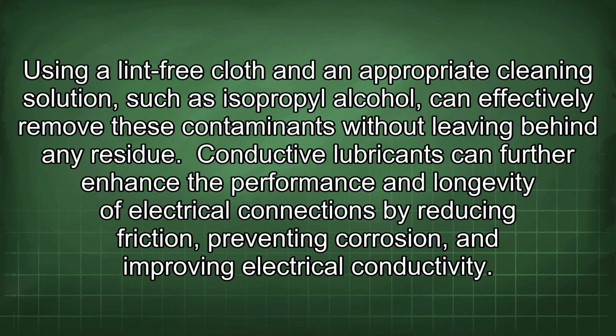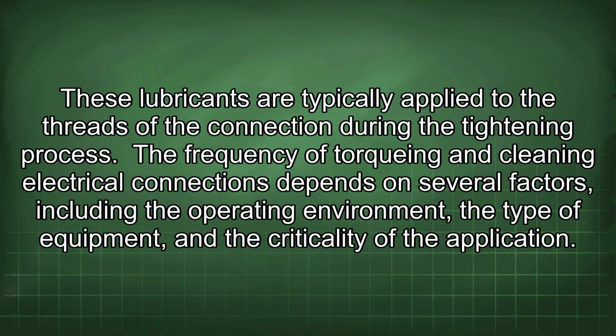Using a lint-free cloth and an appropriate cleaning solution, such as isopropyl alcohol, can effectively remove these contaminants without leaving behind any residue. Conductive lubricants can further enhance the performance and longevity of electrical connections by reducing friction, preventing corrosion, and improving electrical conductivity. These lubricants are typically applied to the threads of the connection during the tightening process.